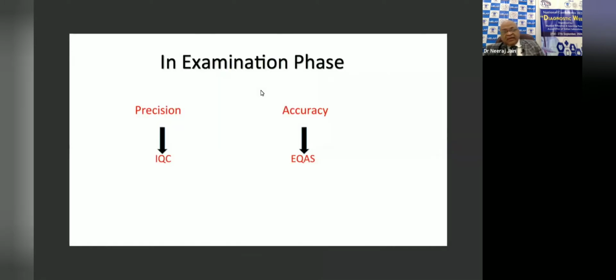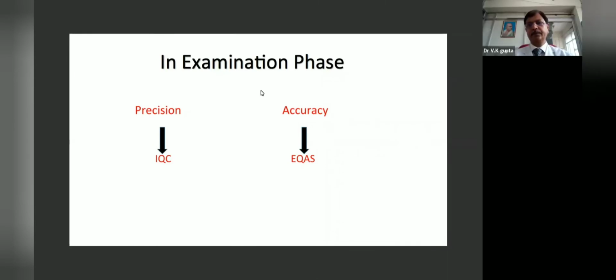These things, mean, standard deviation, and coefficient of variation, we calculate with our quantitative IQC data, because we are getting multiple data points only in IQC. EQAS sample we are running only once, so we cannot calculate any mean or standard deviation in our laboratory. With IQC we get information about precision, how close our results are to each other. With EQAS we get information about accuracy, how far away we are from the target value. So both are important, precision as well as accuracy.